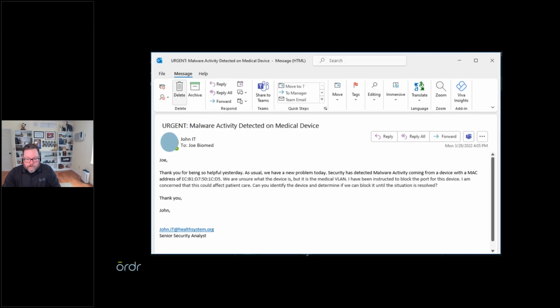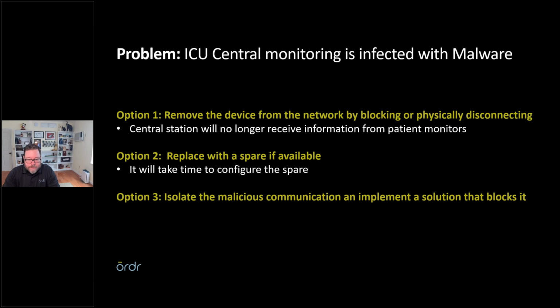So with that, we'll look at this problem just like I ran through there. Our options were to remove the device from the network and physically block it. The central station will no longer receive information on the patient monitor. So you'll have a central station that is pretty much useless at that point in time. It cannot receive the information that is supposed to be monitored from the patient, and then it can't reach out to send that information to wherever it needs to go.